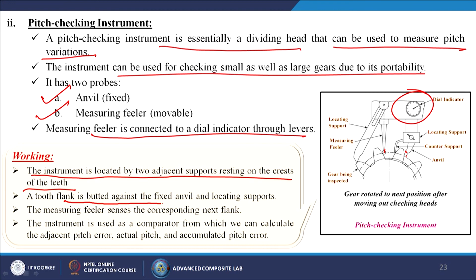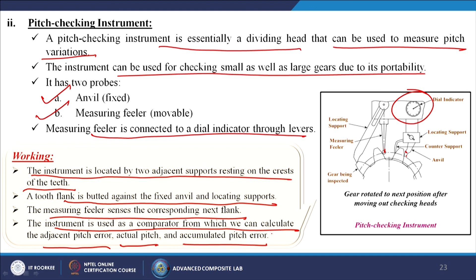So how is it working? The instrument is located by two adjacent supports resting on the crest of the teeth. A tooth flank is butted against the fixed anvil and locating supports. The measuring feeler senses the corresponding next flank. The instrument is used as a comparator from which we can calculate the adjacent pitch errors, actual pitch and the accumulated pitch error. So this will give you this kind of information.